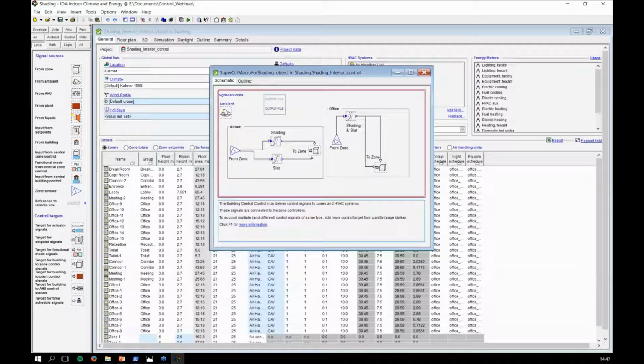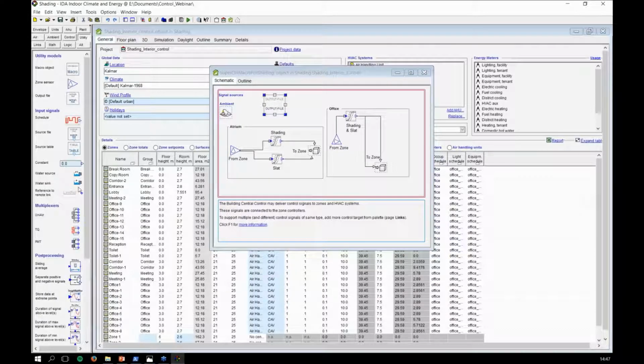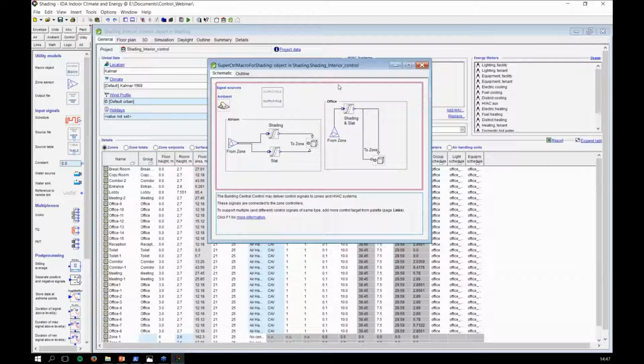One good practice here, whenever you're creating a control macro, is that I always put an output file. You can find the output file in the utility section. The output file will allow me to log all the variables and see how my control structure is behaving. This is very, very good when you're debugging and seeing what went wrong in your system. So that's all I have to do in the supervisory control, basically. It's just measuring the daylight sensor inside the room, one in the atrium and one in the office.